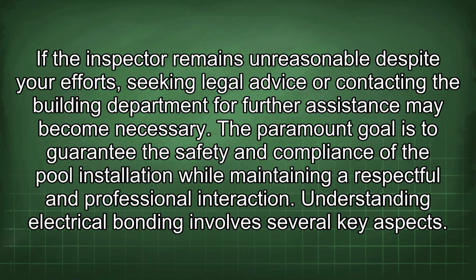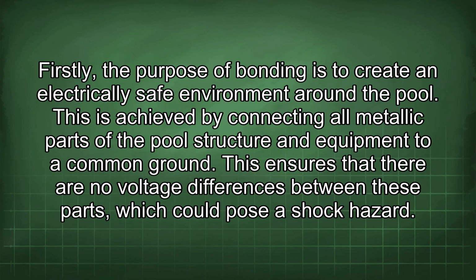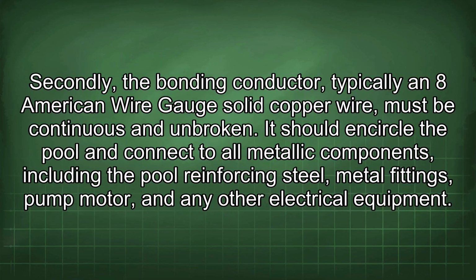Understanding electrical bonding involves several key aspects. Firstly, the purpose of bonding is to create an electrically safe environment around the pool. This is achieved by connecting all metallic parts of the pool structure and equipment to a common ground. This ensures that there are no voltage differences between these parts, which could pose a shock hazard. Secondly, the bonding conductor, typically an 8 American wire gauge solid copper wire, must be continuous and unbroken. It should encircle the pool and connect to all metallic components, including the pool reinforcing steel, metal fittings, pump motor, and any other electrical equipment.